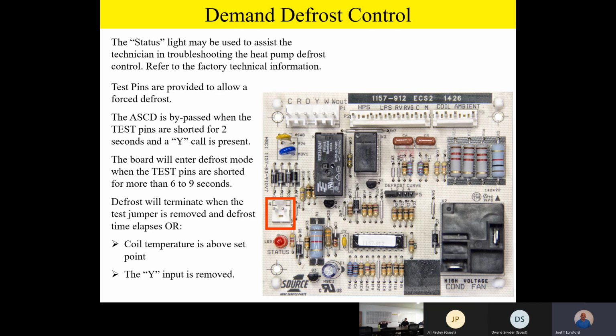It should be noted, though, that when you jumper those test pins, you're going to ignore the sensors. So if you're going to use a physical wire jumper, don't forget to take that wire jumper off before you walk away, because if you don't, the thing will go into defrost and stay there until you remove that jumper. Whenever you jumper those test pins, it ignores the sensors. And remember, team, we terminate defrost by looking at the coil temperature sensor. So if we force a defrost with these pins and I hold that jumper on there, it's going to keep on defrosting until I remove that jumper and it starts to look at the coil temperature again for normal termination.